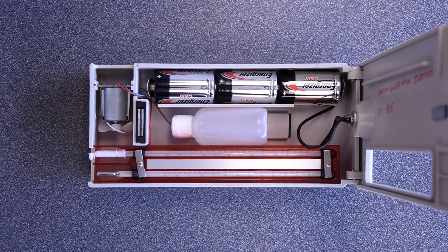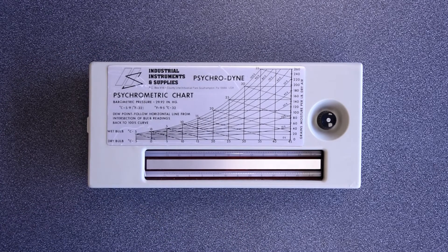To measure temperature and relative humidity with an aspirating psychrometer, place the instrument on a horizontal surface with the thermometers facing up.